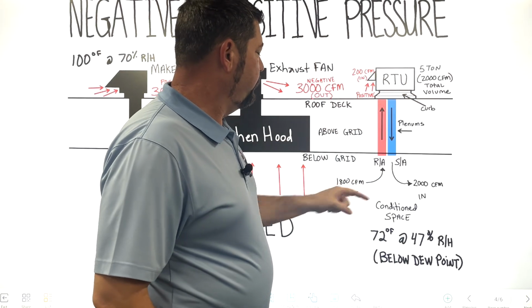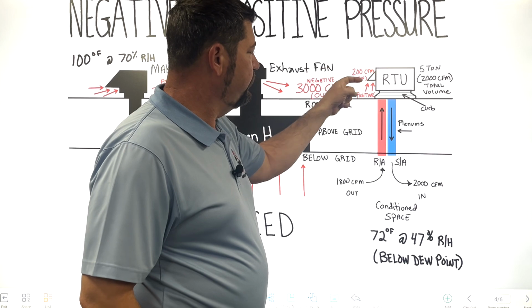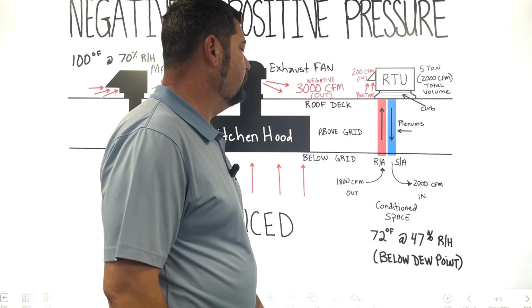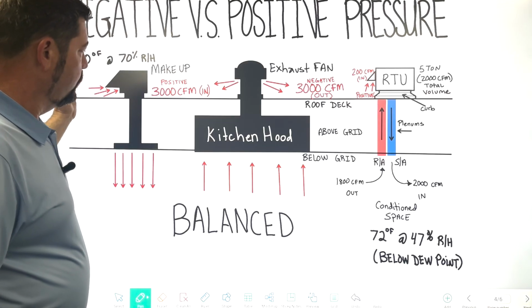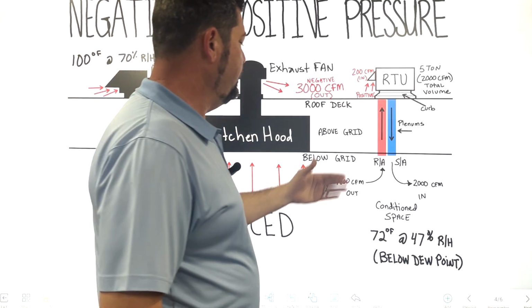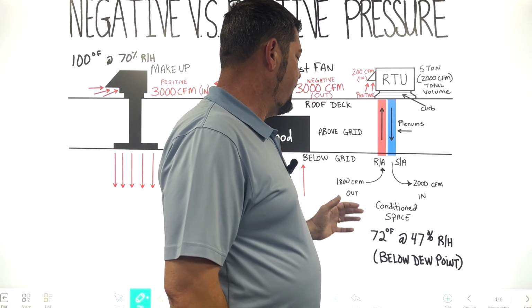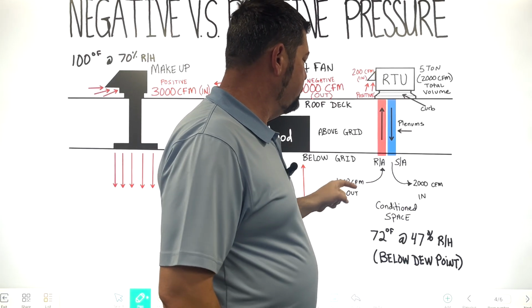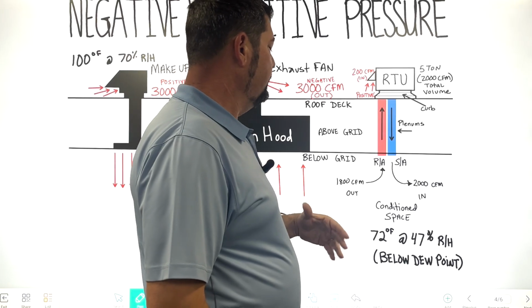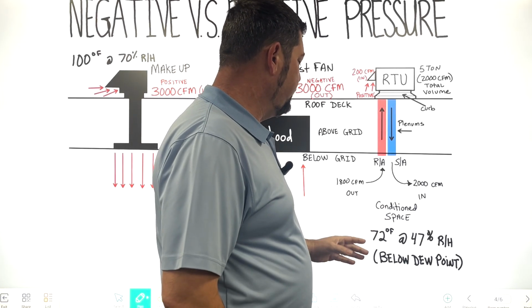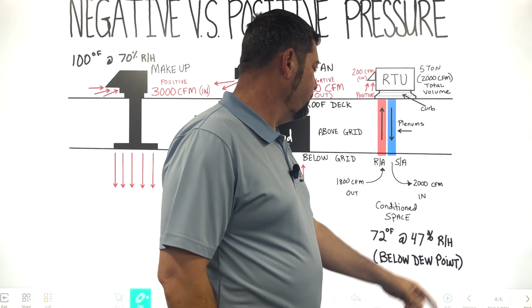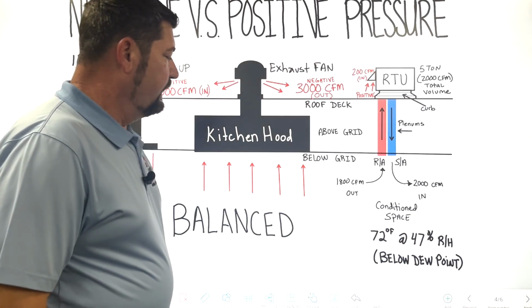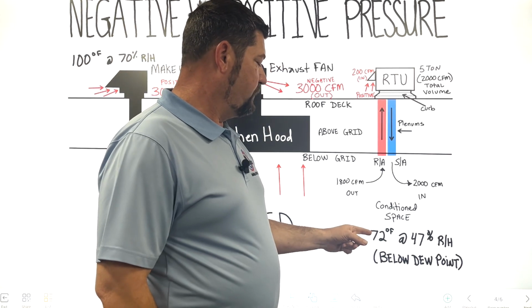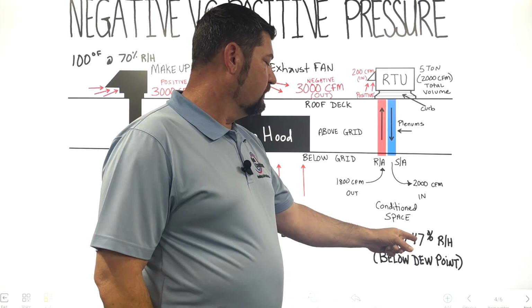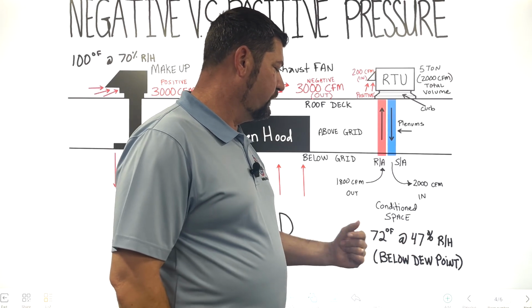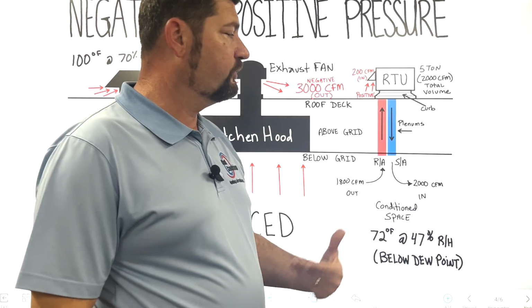But this is the 2,000. So we have 1,800 going in. We're adding 200 CFMs to it, and our total volume is still 2,000 CFMs. Now we're balanced here because we're 100% in, 100% out. But here we're pulling less air out of the structure, and we're adding 200 CFMs into the structure that was not there. All right. Now, if you look at what I have here for our conditioned space, I have 72 degrees at 47% relative humidity. That's below dew point, right? And so it's when this temperature either has to drop or that humidity has to go up. And when they get really close, we're going to hit a dew point and things are going to start to sweat and water's going to start to fall.